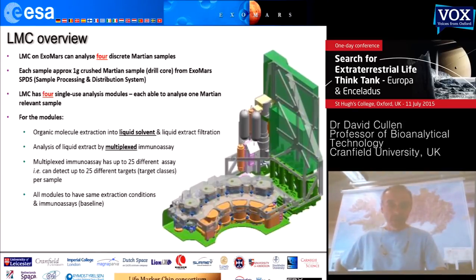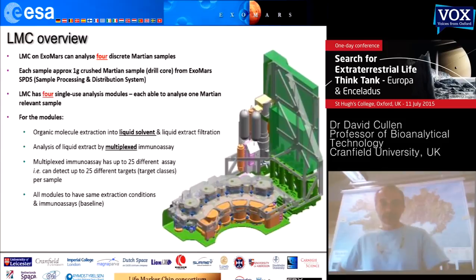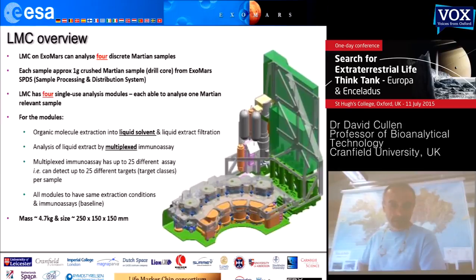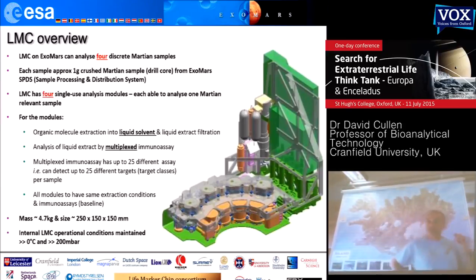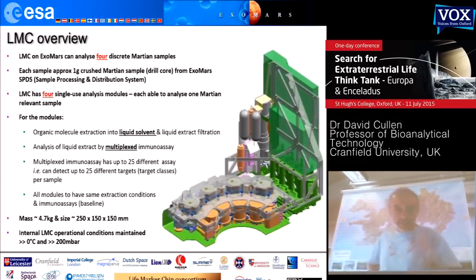That liquid extract was then fed into another part of the system where multiplexed immunoassay happened. Multiplexed simply means we were detecting more than one chemical target structure per analytical system — in fact, we would detect 25 different targets, all multiplexed together into a single assay. For ExoMars, it was just under five kilos. Because we're using aqueous-based solvent, the internal analytical pathways were all above zero degrees C and pressurized to greater than 200 millibars to allow stable liquid water handling.